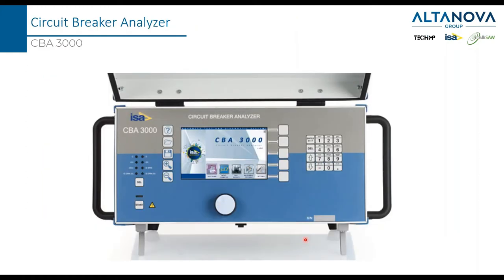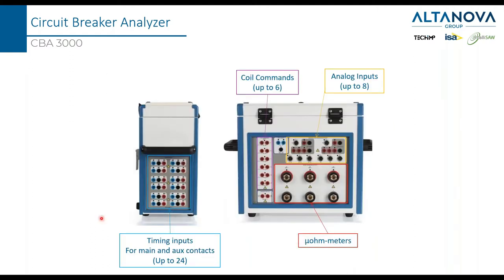For proper tests, we suggest the use of our circuit breaker analyzer called CBA 3000 — our latest device, provided with a built-in PC so you don't need a laptop to operate it. There is a section to connect the main and auxiliary contacts for timing measurement, a part to connect the coil commands (up to six), a section that generates the current, and a section where we measure voltage for the micro-ohmmeter test in order to measure resistances.